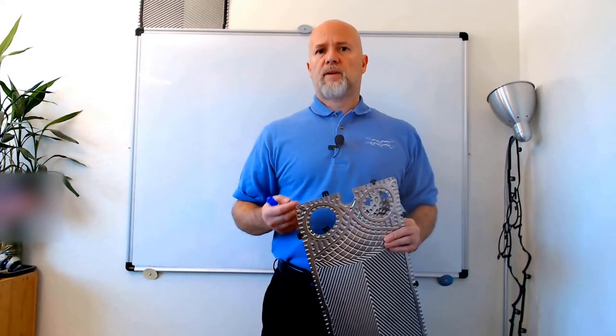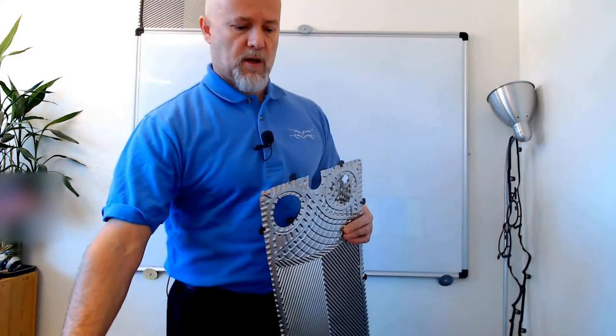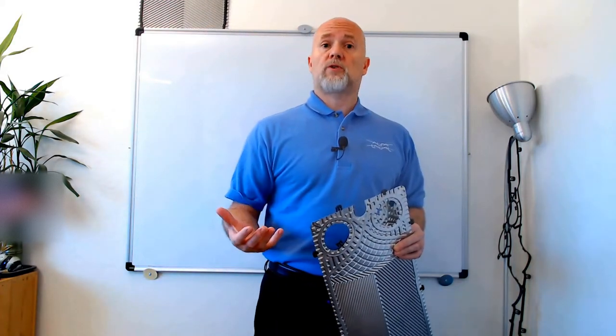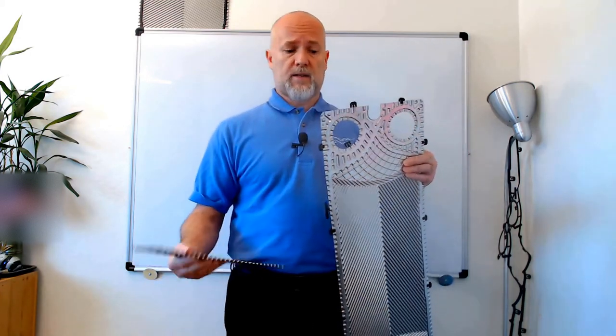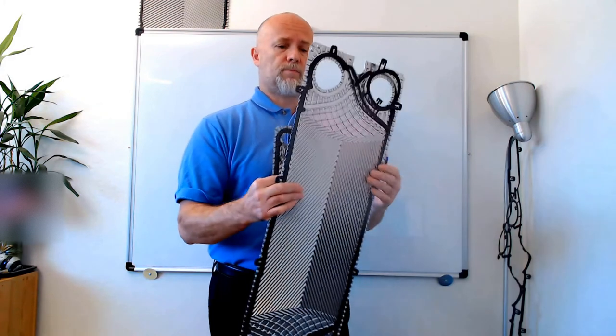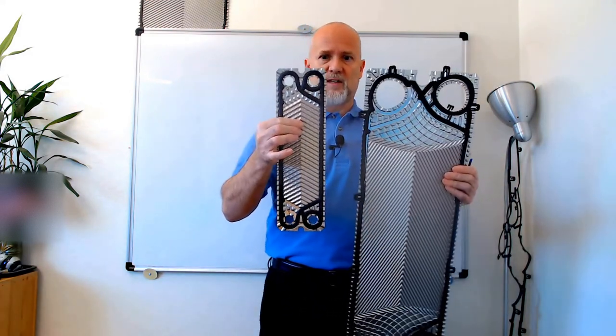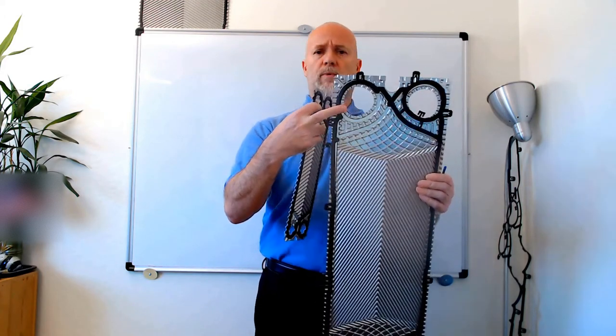Let me spend a few moments to talk about the difference of the size connections. You do not want pressure drop at the ports. If you look at these two plates, these are two gasketed plate and frame heat exchangers, you can see very different ports. This is one inch, this is two inches or three inches probably.